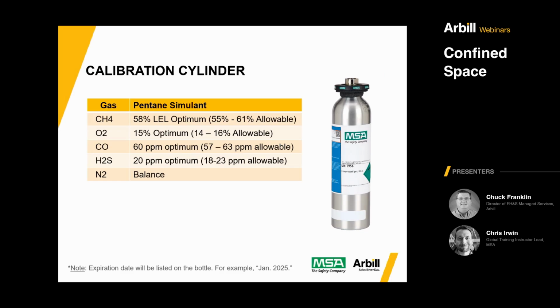Here's the example of calibration gas. It'll tell you on the label what is in that bottle. That is specific to the test on the detector. When you put it into test mode, or when the detector's starting up, it'll tell you specifically what quantities of gas it's looking for. If the numbers on the screen are different from what's on the bottle, once again, it will mess up the test. So you need to make sure you've got the proper gas that matches what the detector actually thinks it's looking for, for that entire process to work.